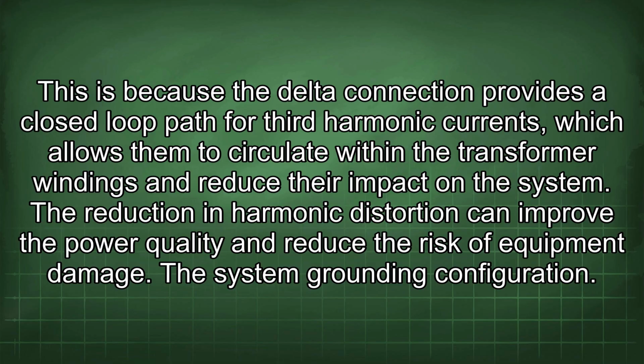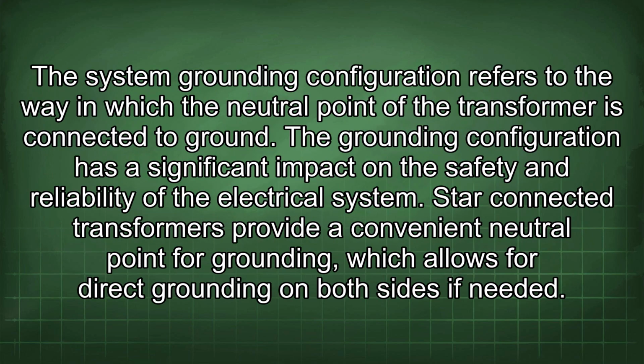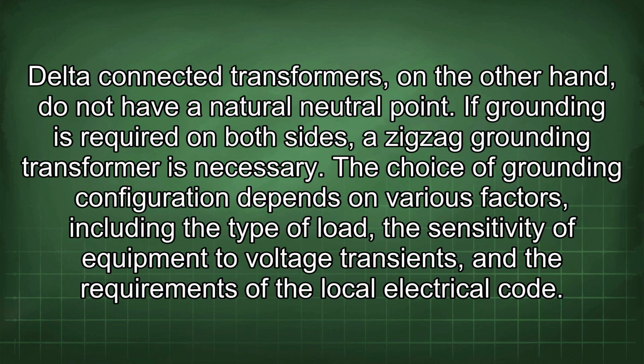The system grounding configuration. The system grounding configuration refers to the way in which the neutral point of the transformer is connected to ground. The grounding configuration has a significant impact on the safety and reliability of the electrical system. Star-connected transformers provide a convenient neutral point for grounding, which allows for direct grounding on both sides if needed. Delta-connected transformers, on the other hand, do not have a natural neutral point. If grounding is required on both sides, a zigzag grounding transformer is necessary.